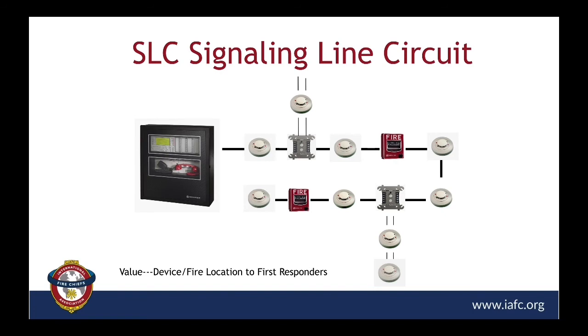through this SLC loop. And here's another good picture on the next slide. The dotted line represents a single pair of wires. You see it going through a smoke detector. Then it goes to this addressable module, which in this case is picking up a conventional smoke detector. It could also be the conventional water flow or tamper switch. You see that SLC, that pair of wires, going through the building, another smoke detector, a pull station, another addressable module.